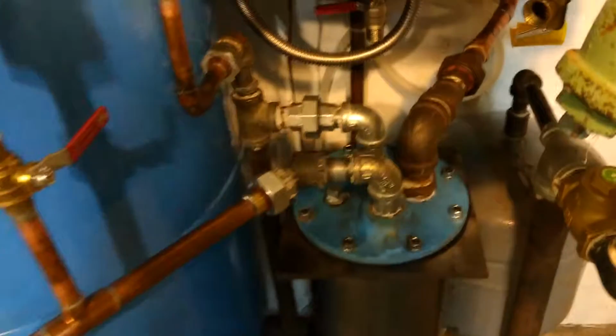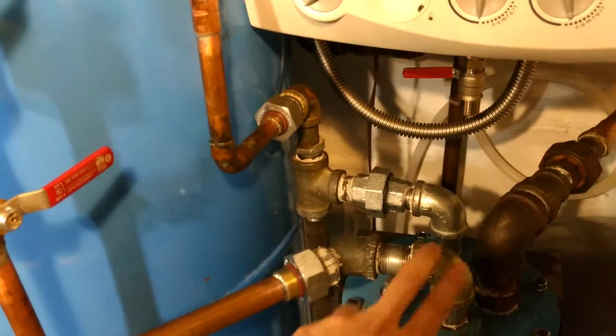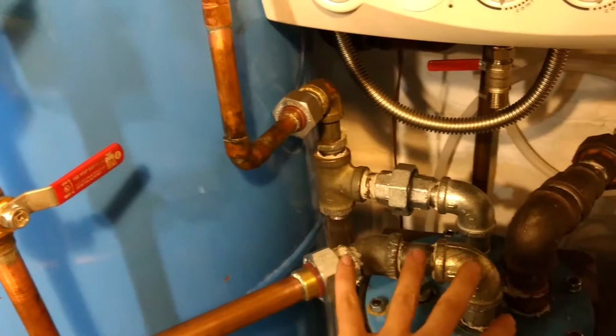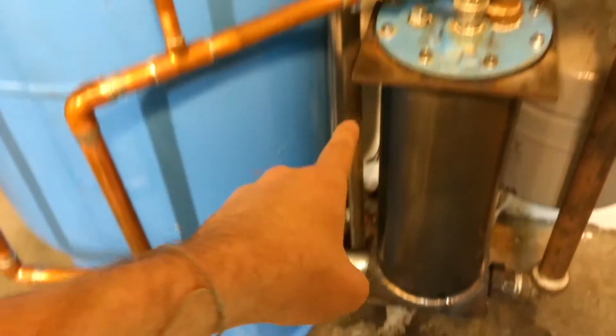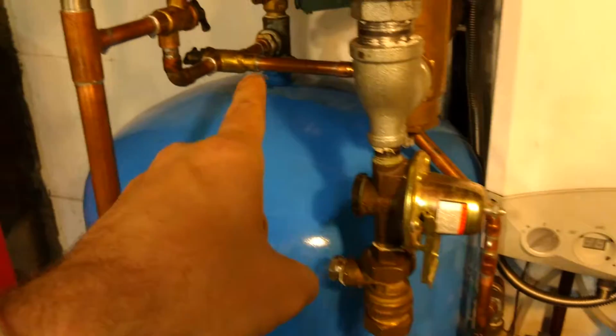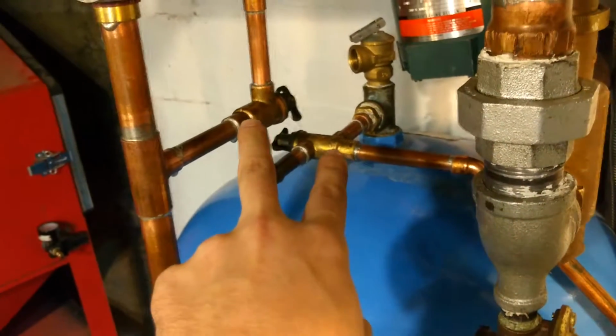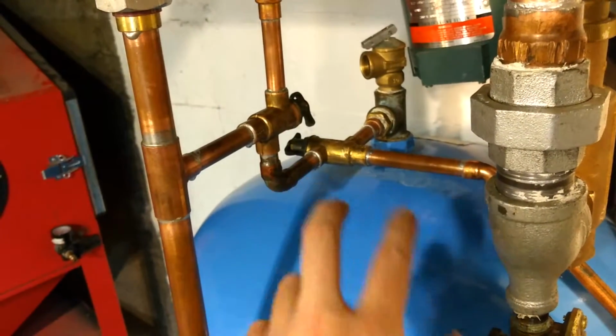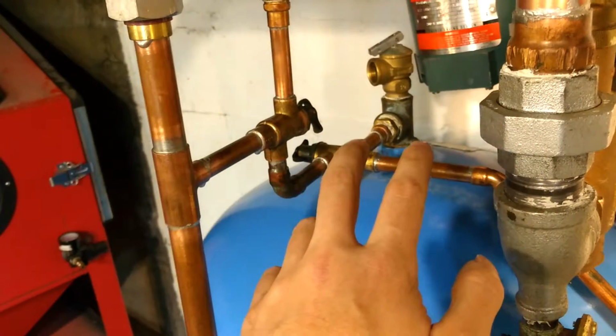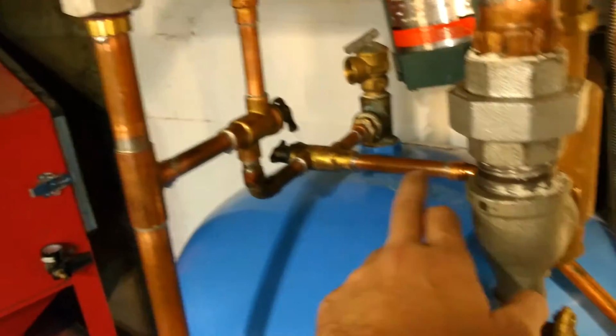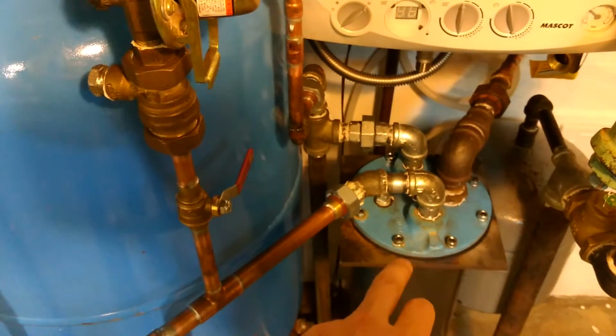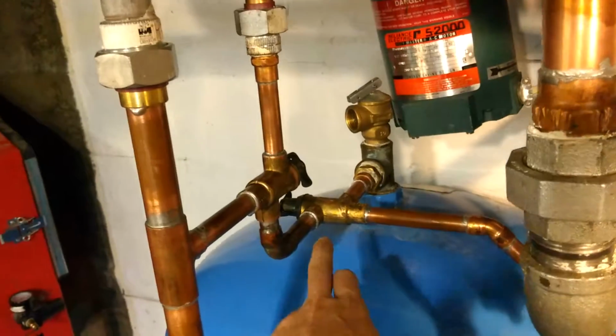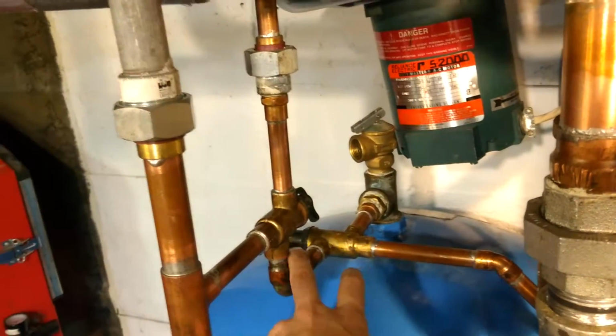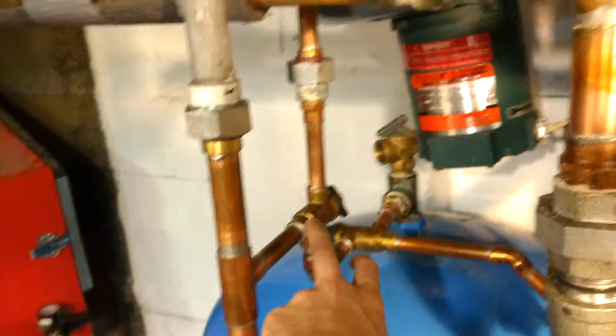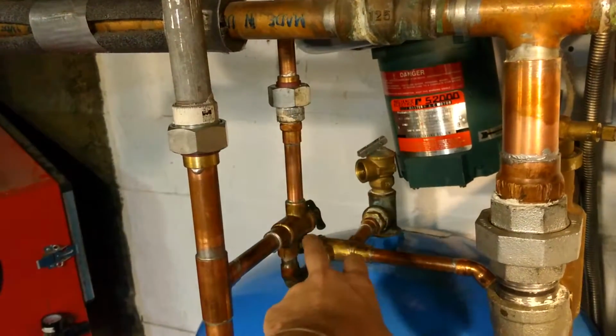So in order to implement this, this is the main inlet to the whole hot water system, the drinking hot water system, and the outlet goes down into the tank, unrestricted, or up to the top here, and into a set of two thermostatic valves. So the reason I used two valves was, if the temperature of the tank is higher than the valve is calling for, then it is going to take whatever heat is available from here first and dilute the hot water here and use very little from the tank, and then it is going to cool it down even further with this secondary thermostatic valve before the main hot water to the house leaves.